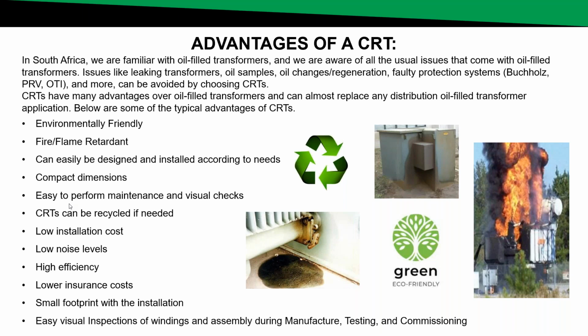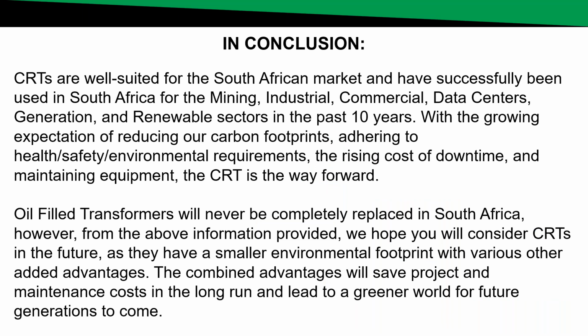Again, it's very easy to do visual inspections of the windings and assembling during manufacturing, testing, and commissioning. Usually when you order an oil transformer and you go and do the testing, it's already closed and they just test the transformers for you, and you can't actually see what's happening inside the unit. With cast resin transformers, you are able to actually see the windings and see the connections, which is a major advantage.